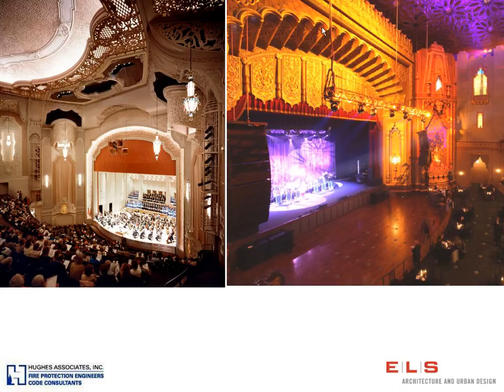Yeah, so one of the things that I didn't mention when we were talking about the California Historical Building Code was that when you install fire protection systems, particularly an automatic sprinkler system throughout the building, it gives you a lot of freedom and flexibility in your design and in maintaining the character-defining features and in not having to comply with the prevailing code. So the sprinkler systems that we install go a very long way, and the language in the California Historical Building Code says sprinkler system throughout.